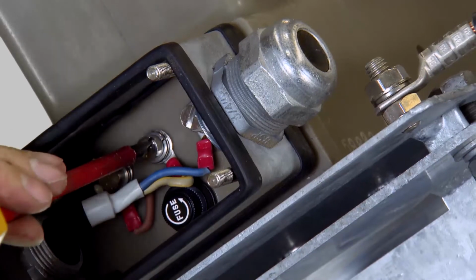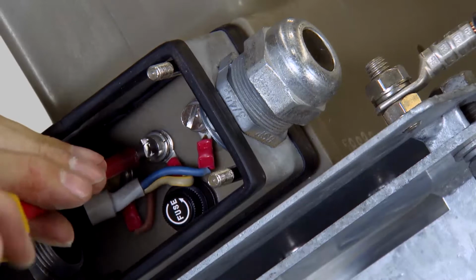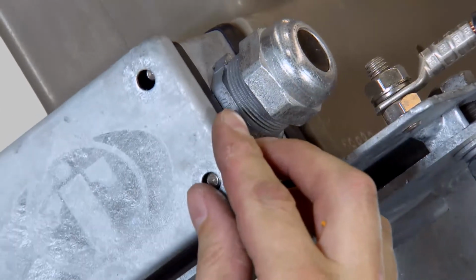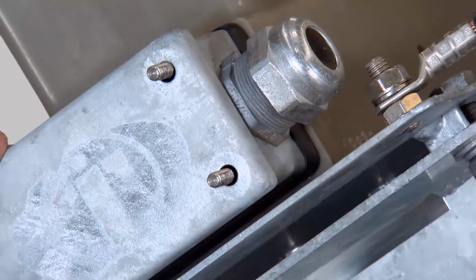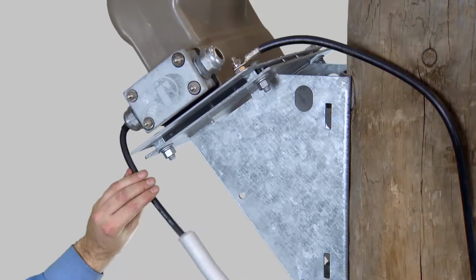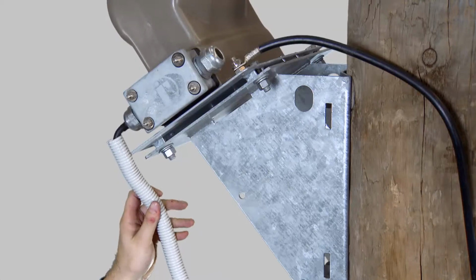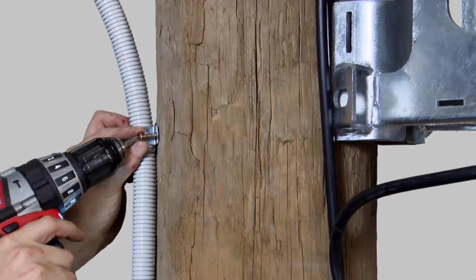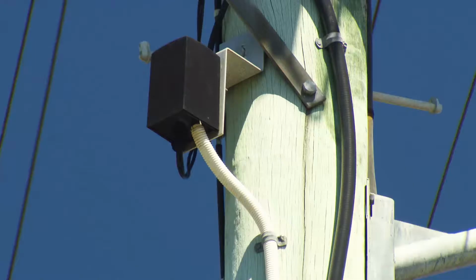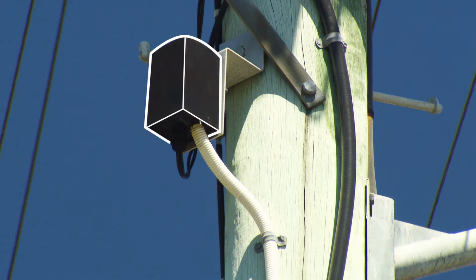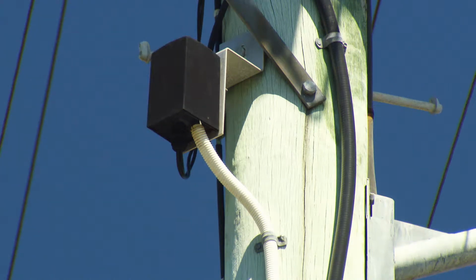Terminate the connections to the VT with proper sized lugs. Fit and secure the cover, making sure the gasket is in place. It's recommended to have external protection for the cable. Secure the cable to the pole at regular intervals. A double pole isolation point is recommended so the RC10 can be isolated from the low voltage supply.